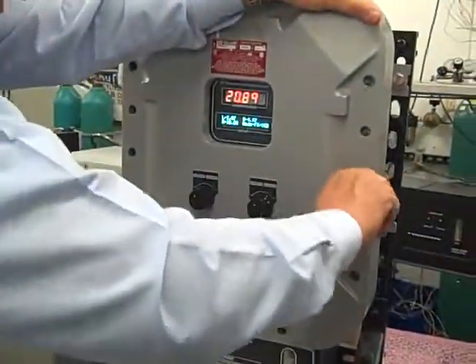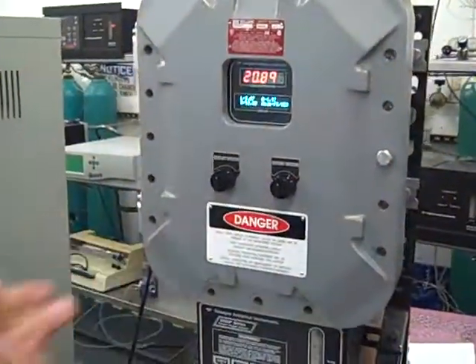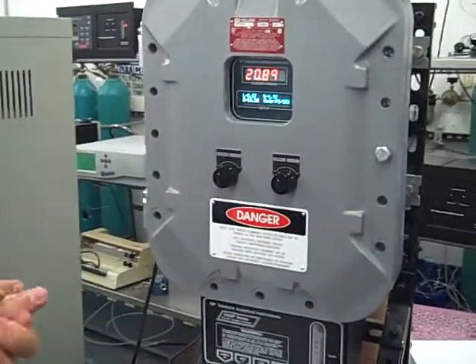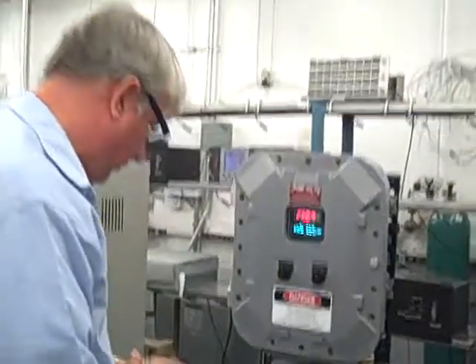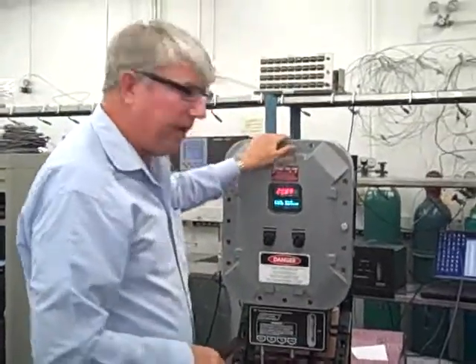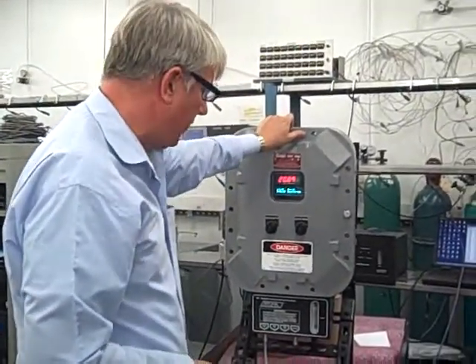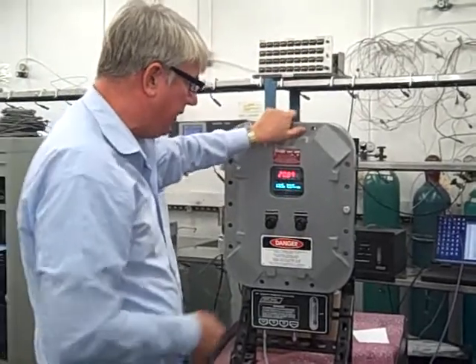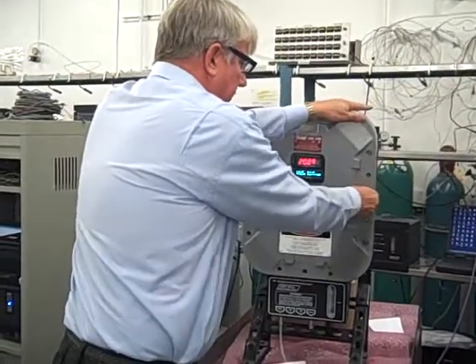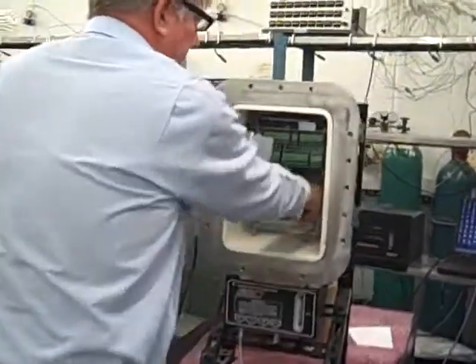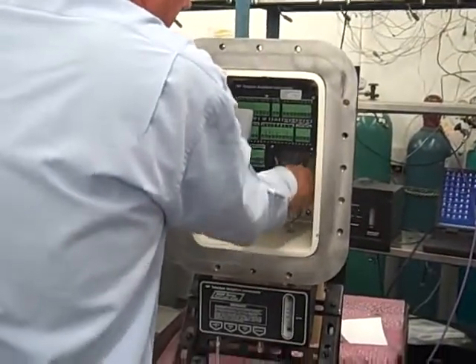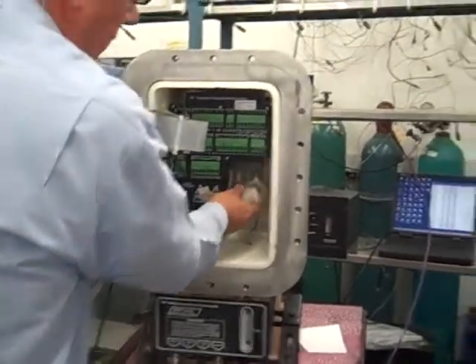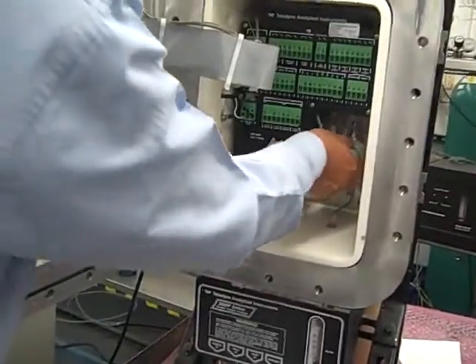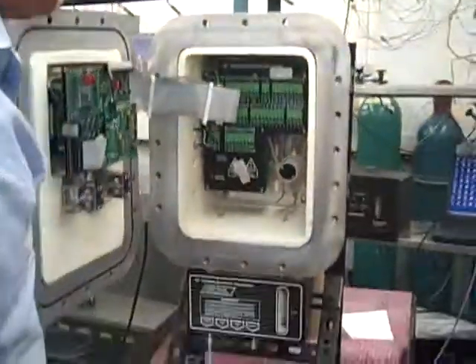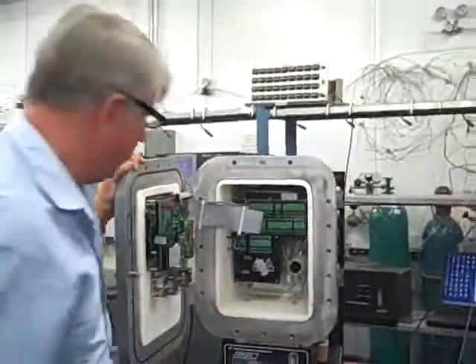The other thing we want to talk about is maintenance. Generally speaking, these units require very little maintenance except the occasional replacement of the sensor. But in petrochemical applications, one wants to look particularly for buildup of water or debris. So you want to occasionally inspect your sensor holder to make sure there are no signs of water and debris in there. But for air separation applications, generally speaking, there's no cleaning required at all.